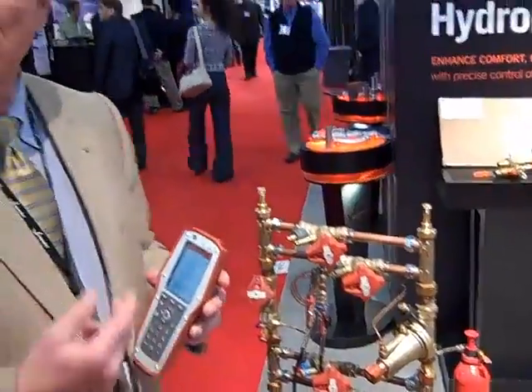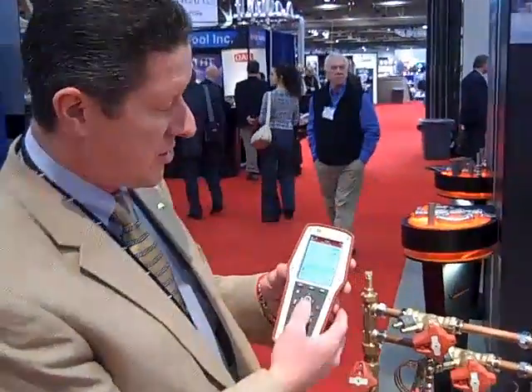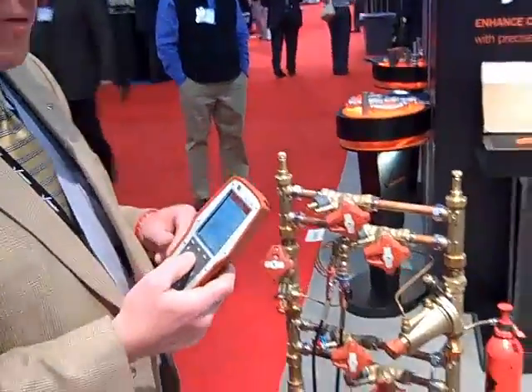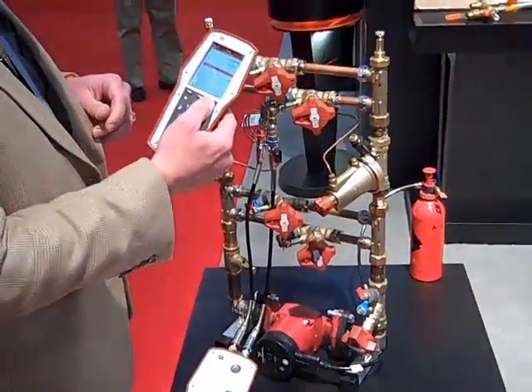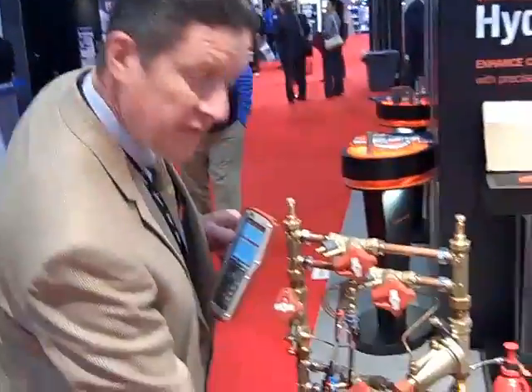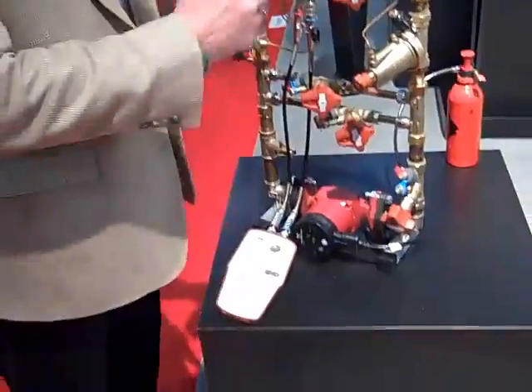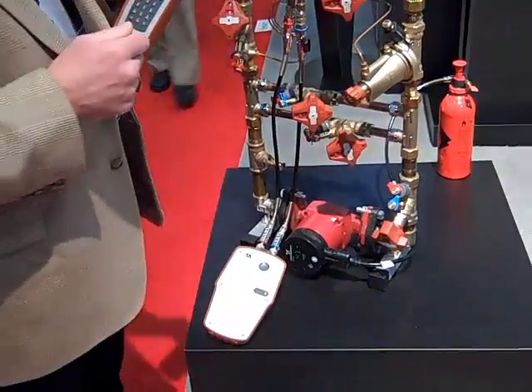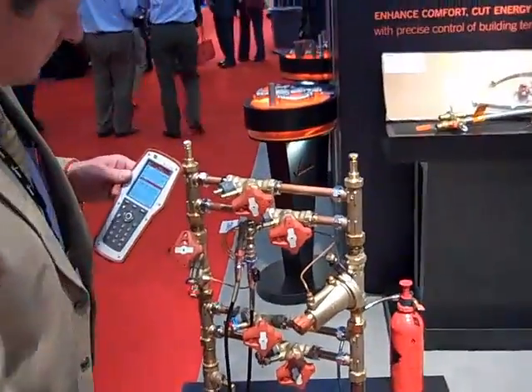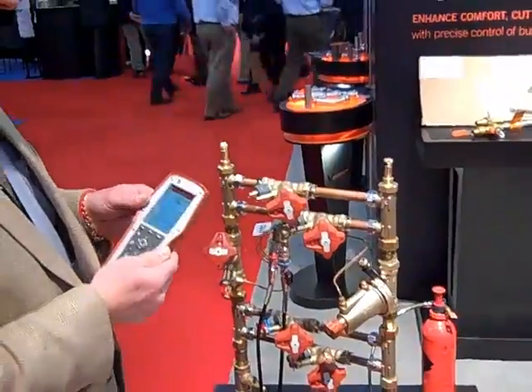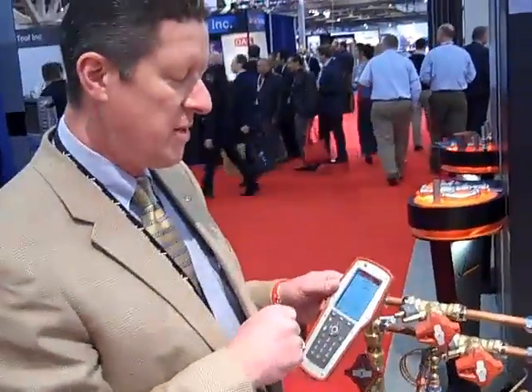If it had ethylene glycol or propylene glycol, we could just scroll down here to water, hit enter, and it'd pop it open, and we can put in 30% glycol solution, okay? And then it'll automatically correct for the flow rate. So we want to measure this valve, so we hit measure. We're measuring a new valve, so we calibrate the sensor, it vents the air in the lines, and we're ready to go. Calibration's ready. So right now we're running 0.8 GPM at 3.55 feet of head. That's how fast we can get a measurement out of this valve.